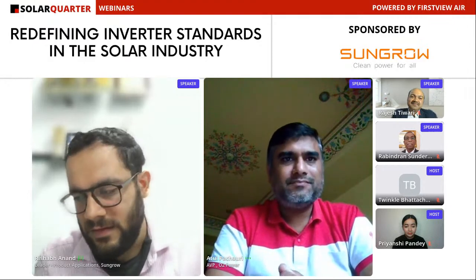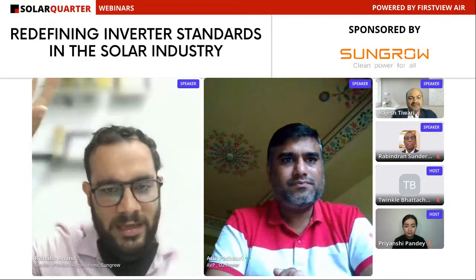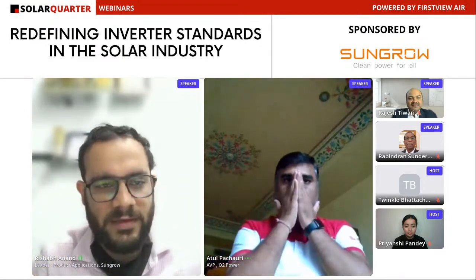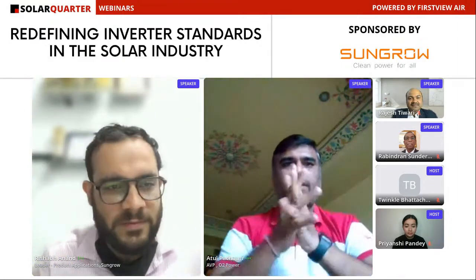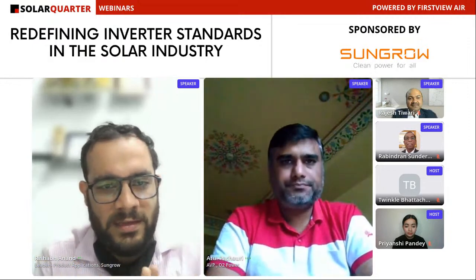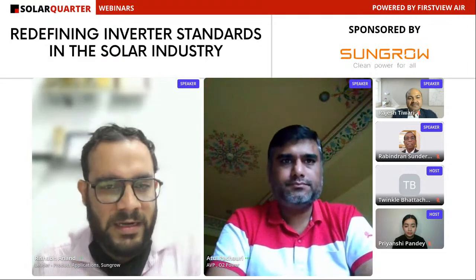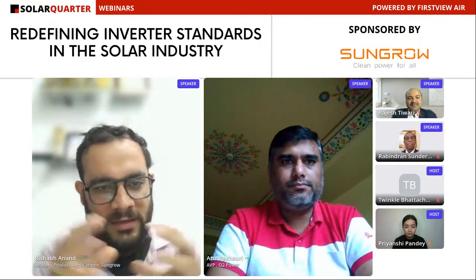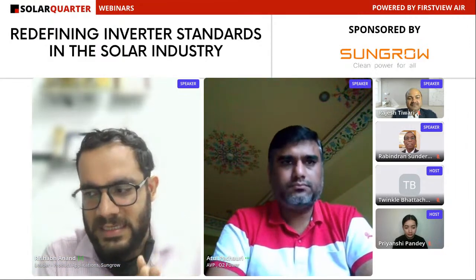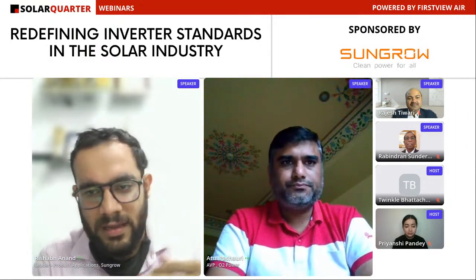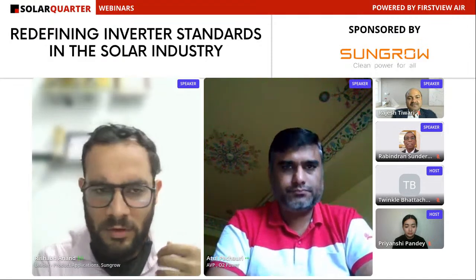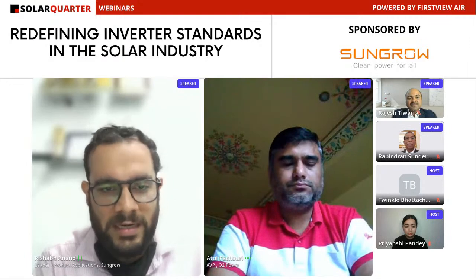As you can see, sir, SUNGROW is trying to bridge the gap. Earlier, central inverters used to be at a very high kVA rating and string inverters at a very low rating. Now you will see the gap is bridging up, the difference is coming closer. You are having almost a 300 kilowatt string inverter, and a central inverter starting at 1.1 megawatt, in multiples of that. So we are trying to bring all the things closer, with special emphasis on plug-and-play solutions, so that no high maintenance or highly qualified maintenance personnel are required at site.